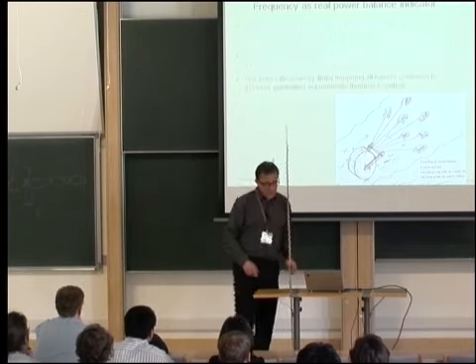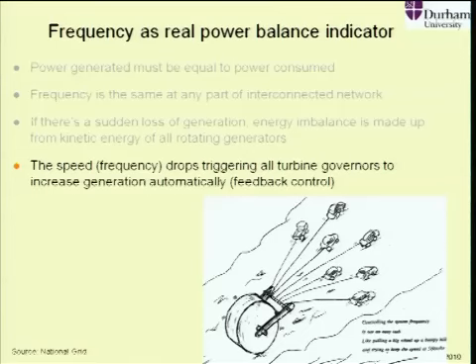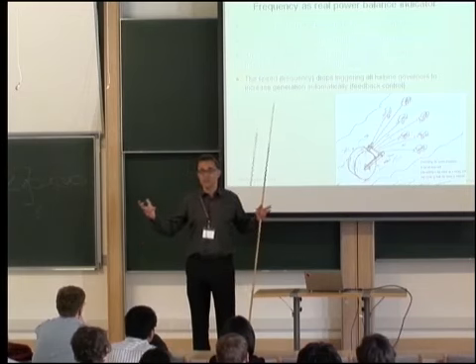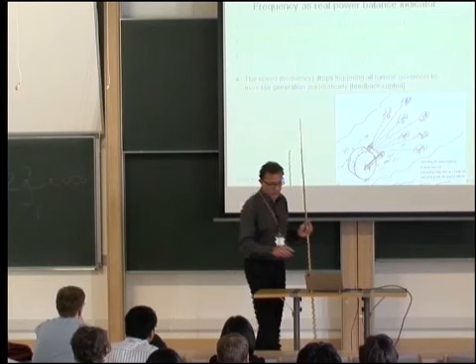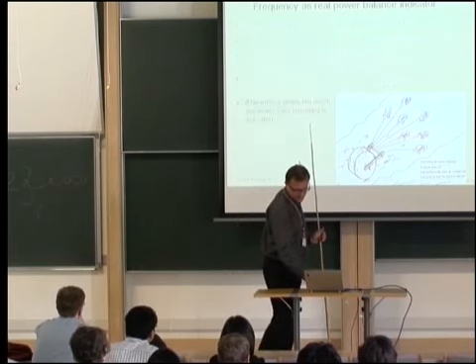As frequency drops, this is picked up by so-called turbine governors, which control generation of individual power stations. They pick up this signal of dropping frequency to automatically increase generation. It's all automatic, without human intervention, and this is how the system has been designed. So basically, the whole system responds to any change in the real power balance.